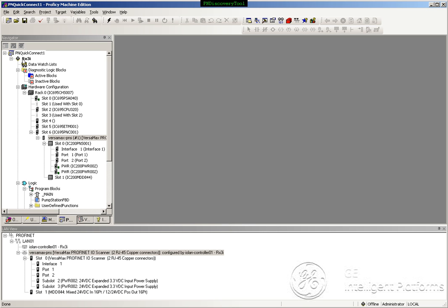So now you notice that I'm offline and the Discovery tool was activated so that you could see that it has nothing to do with the communications with the processor. So I have to be on the PROFINET network to use the Discovery tool. So if you just connected to the Ethernet card, if it's not coupled over, jumpered over to the PROFINET controller, then you will not be able to use the Discovery tool. You have to be on the PROFINET LAN to use it.